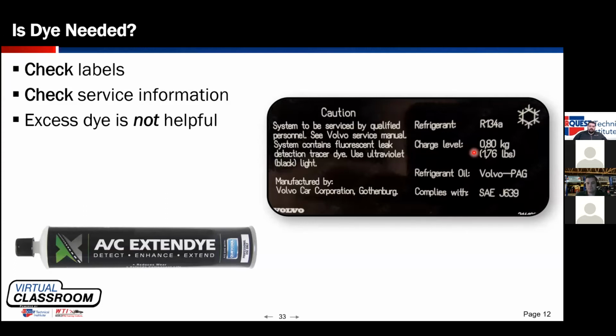Many modern systems, because we're trying to minimize the amount of oil that circulates through the system for better performance, by keeping that oil in the compressor with an oil separator, hold less than 3 ounces. So again, if I just go and put a half an ounce of dye into that system, that could be a 15 to 20% overcharge of oil in the system just because I put dye in. So make sure that if you are going to add dye, you're not adding dye to a system that already has dye in it. An extra dose isn't necessarily helpful. And make sure that you are adding it following the manufacturer's instructions.